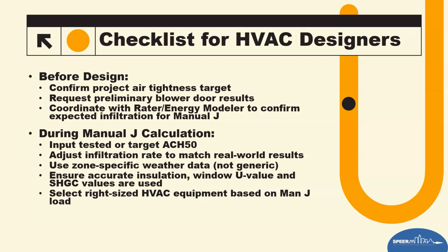So basically you request the preliminary blower door results. In other words, you talk to the builder or the third party that has done work for them before and say, what is normally the air tightness of that building? Do they build a tight house, or do they have a lot of holes in those buildings? So then you coordinate with the energy rater and the modeler, and you confirm the expected infiltration on the Manual J. So then you do a Manual J, you input the tested or targeted ACH, and then you adjust the infiltration rate to match real world results. So you use zone specific data, not generic. You ensure accurate insulation, window values, and SHGC are used and match what the builder is actually installing.